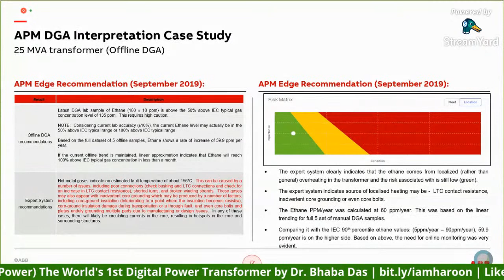And it also said that if this trend is maintained, within 1 month's time you will cross the 100% IEC concentration level. And the expert system says that the hot metal gases are there. Fault temperature is calculated around 150 degrees. You need to check your core bolts, contact resistance. You need to do some tests.